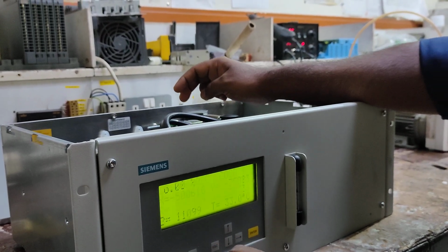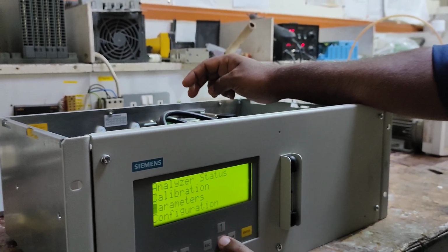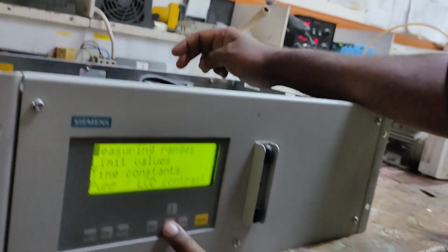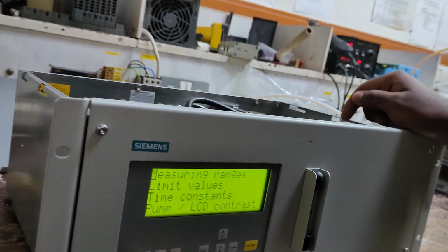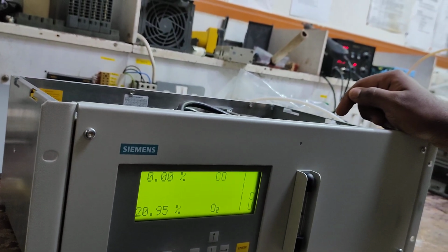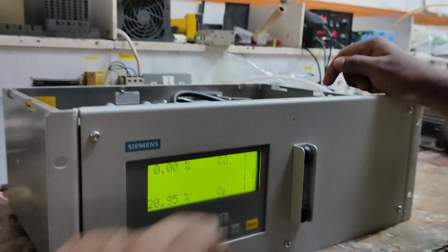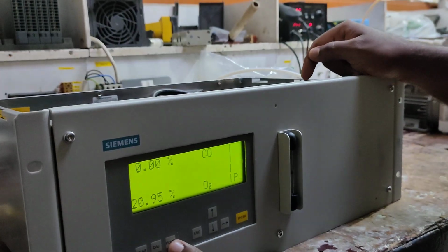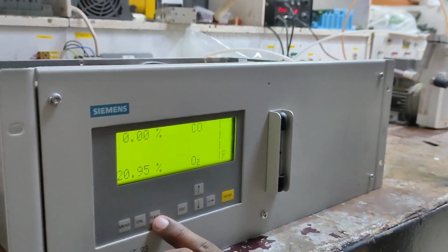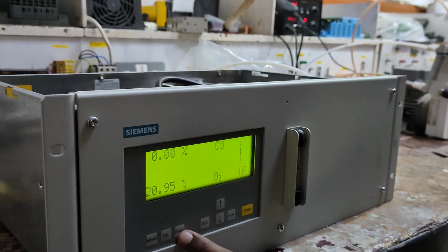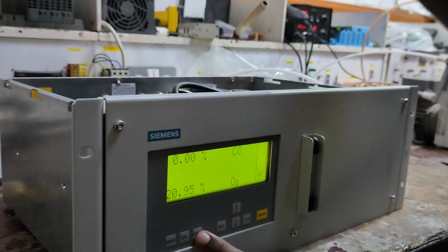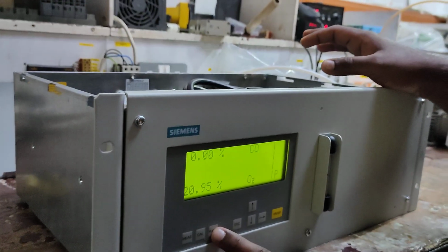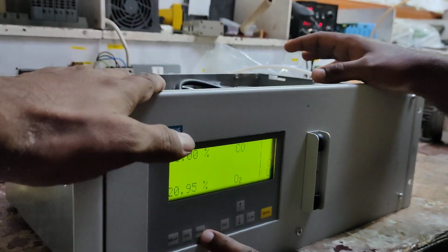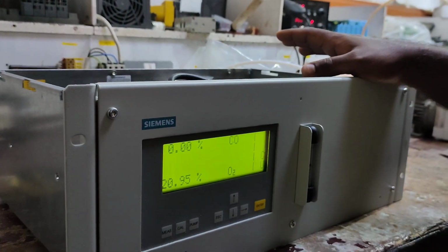So we have seen the measuring ranges, and measuring changes also. Now you don't have any external pump here. If you press this one, nothing will happen. P, pump on, off. You have a digital output; you can use that digital output to run the pump. You can give that input to a PLC or to a relay, and you can run the pump directly. It means there is no inbuilt pump.